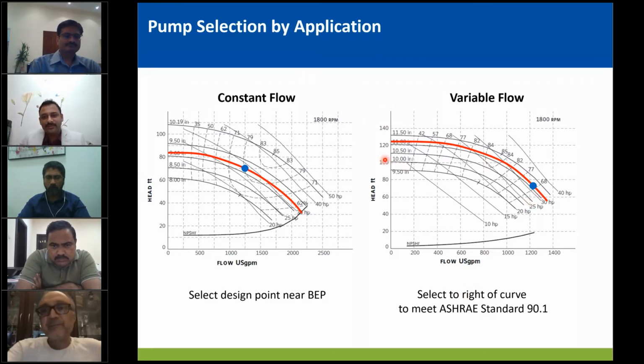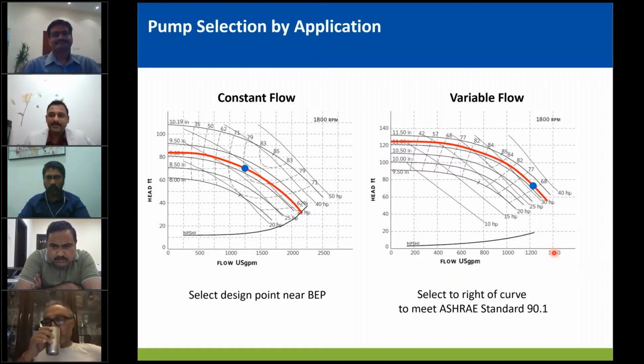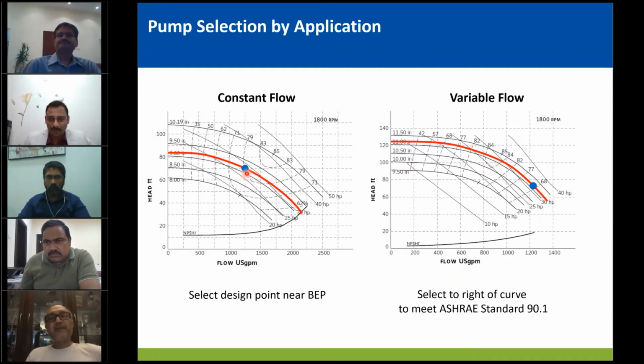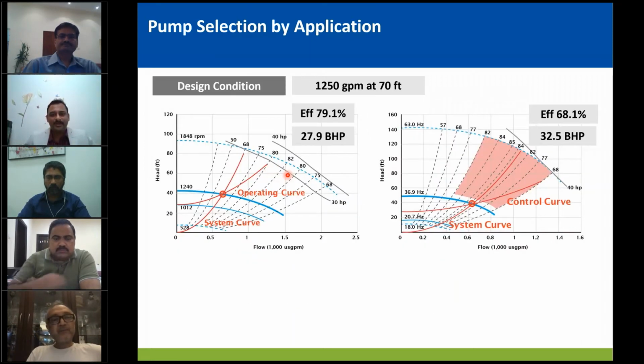Coming to variable flow, we all know HVAC is a part load industry. Chillers are being selected for IPLVs and part load weightages, but often pumps are selected the same traditional way that we select a constant flow pump. That's like the left hand side of what we're showing here. So we want an 80% efficient pump, and when we actually put that pump into operation, it's not operating at that particular point for a variable flow system. So let's look at how it operates. This is a variable flow comparison.